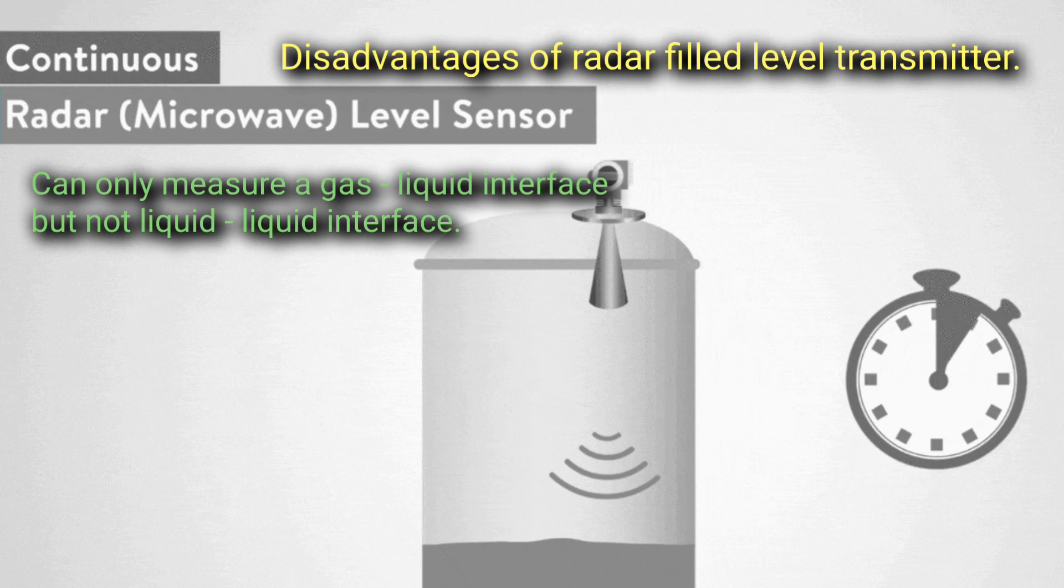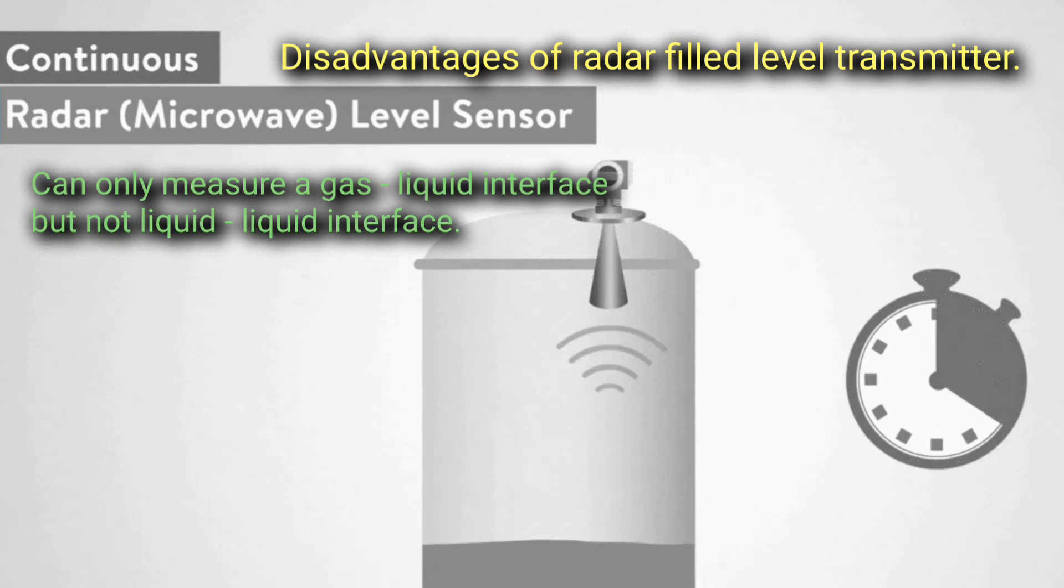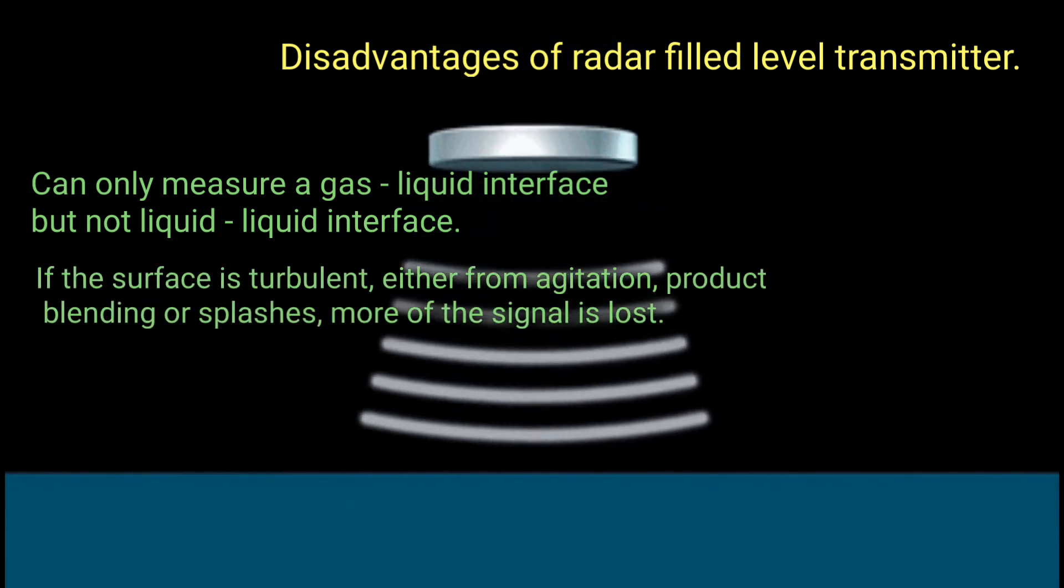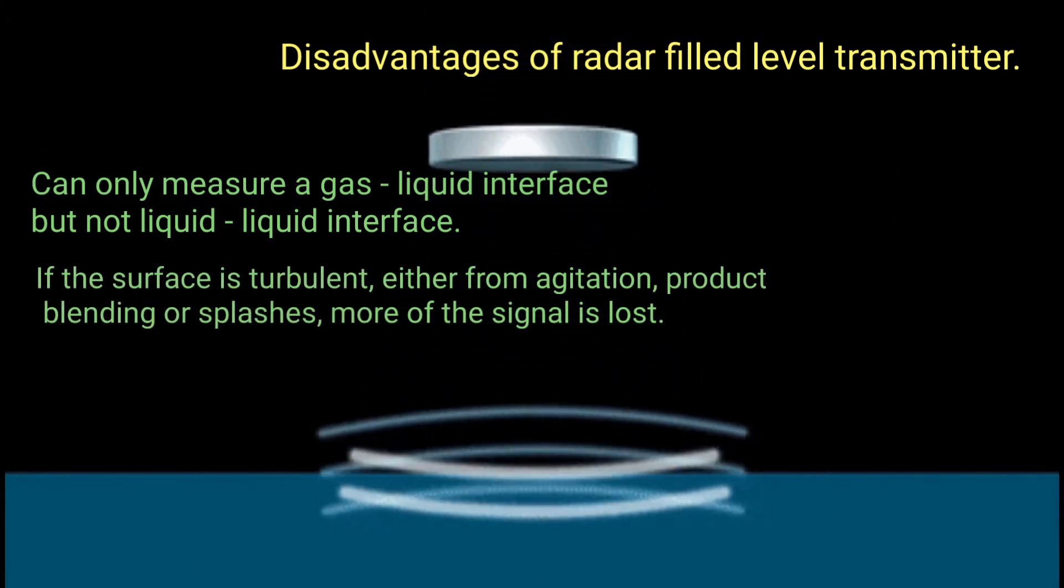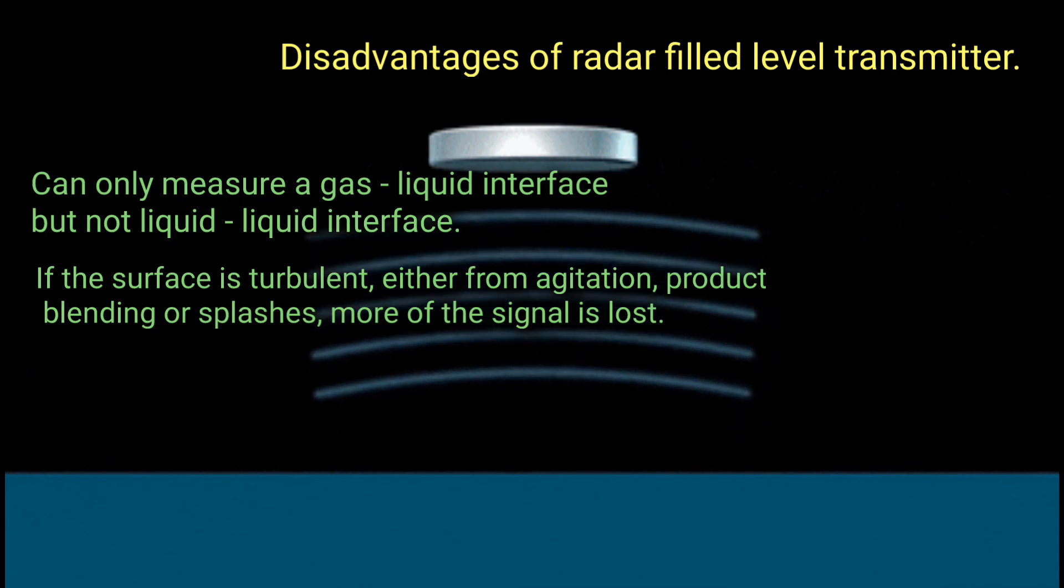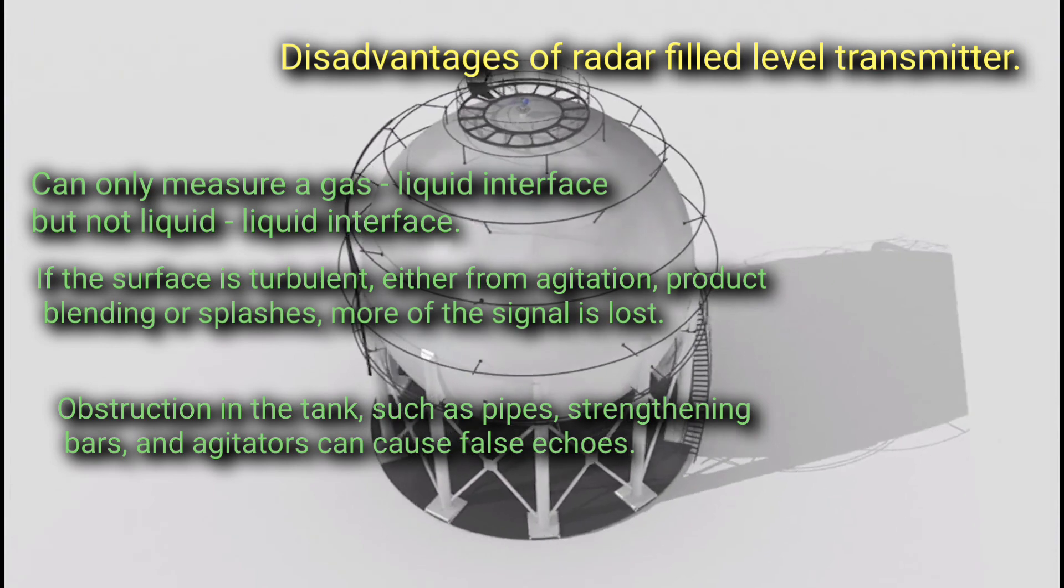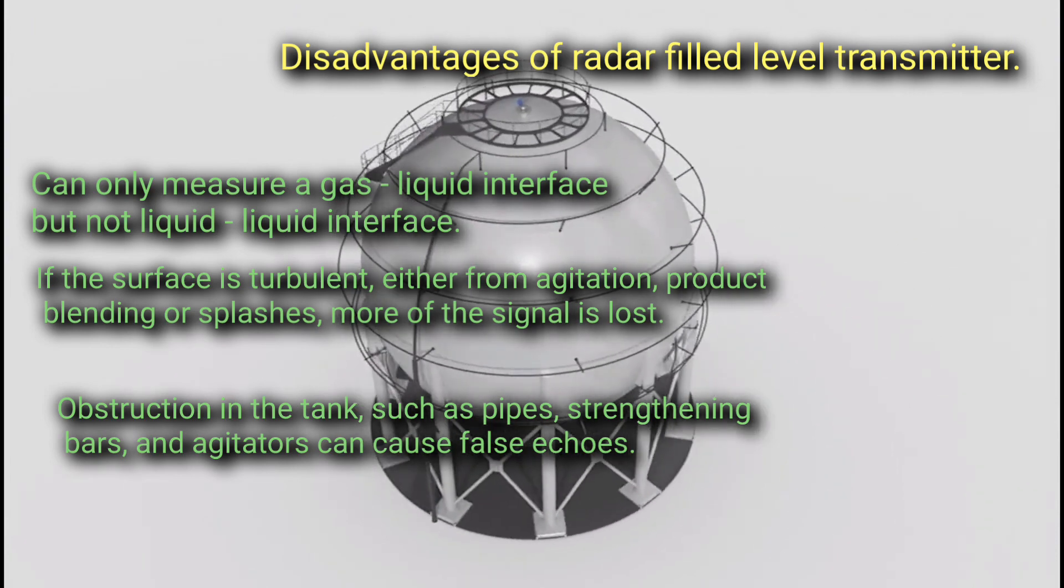Disadvantages of radar fill level transmitter: Can only measure a gas-liquid interface but not a liquid-liquid interface. If the surface is turbulent either from agitation, product blending, or splashes, more of the signal is lost. Obstructions in the tank such as pipes, strengthening bars, and agitators can cause false echoes.